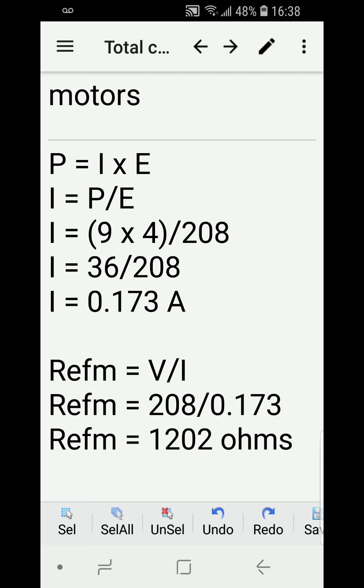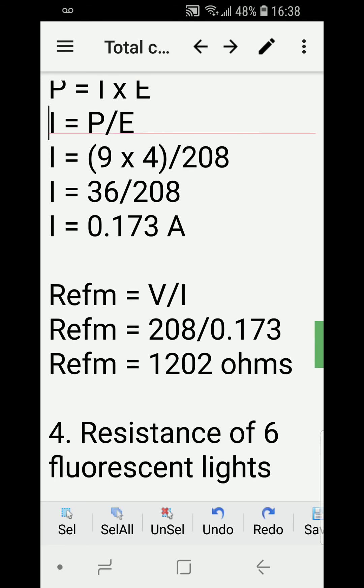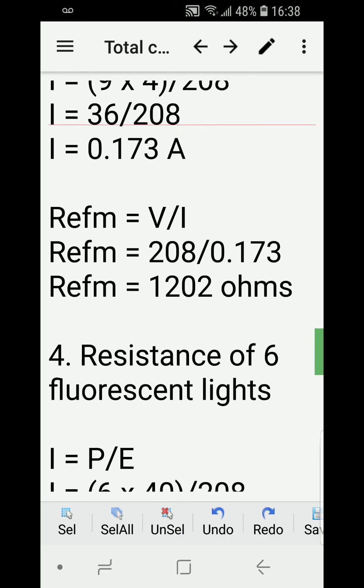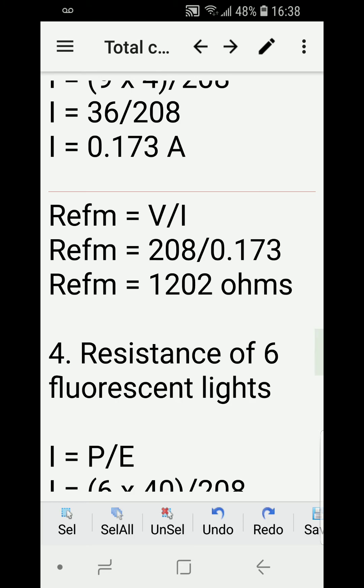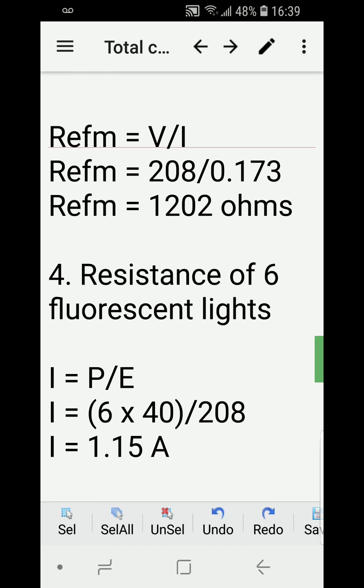We know the power formula is P equals I times E, but in this case we're solving for I, so I equals P divided by E. For the four evaporator fan motors: 9 watts times 4 divided by 208 volts gives 36 over 208, which equals 0.173 amperes. Now we solve for resistance: voltage over current equals 208 over 0.173, giving a resistance of 1202 ohms for the evaporator fan motors.